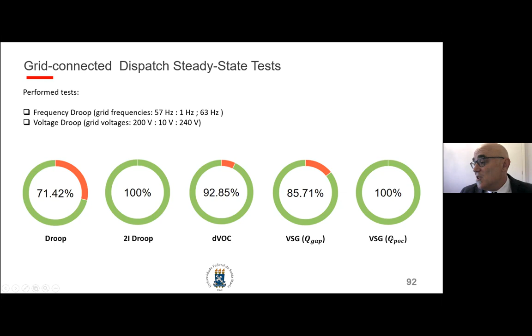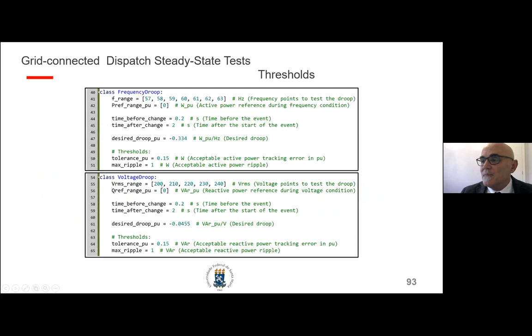So this is one important point. Here the frequency has been changing from 57 to 63 Hz, and the voltage has been increased from 200 volts to 240. The results are summarized over here. This is not bad. The virtual synchronous generator with the feedback of the reactive power at the PCC also did well. Each one of those points is one simulation that has been captured, analyzed, and plotted.